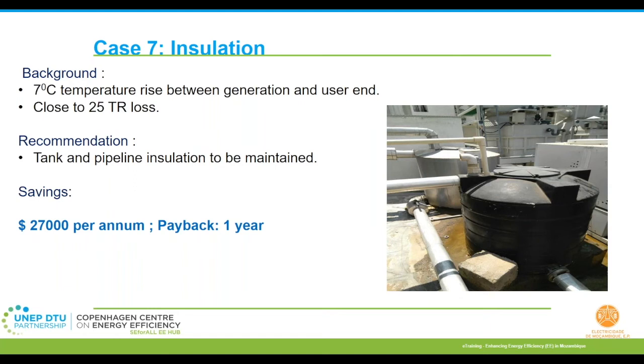So we found in one facility that they had two such tanks. Unfortunately, one was completely and properly insulated and the other one was not. It was probably a delayed maintenance schedule or negligence. So the simple principle was just to insulate this tank. After the insulation, they noticed that close to $27,000 per annum in energy cost savings has been achieved in this regard.